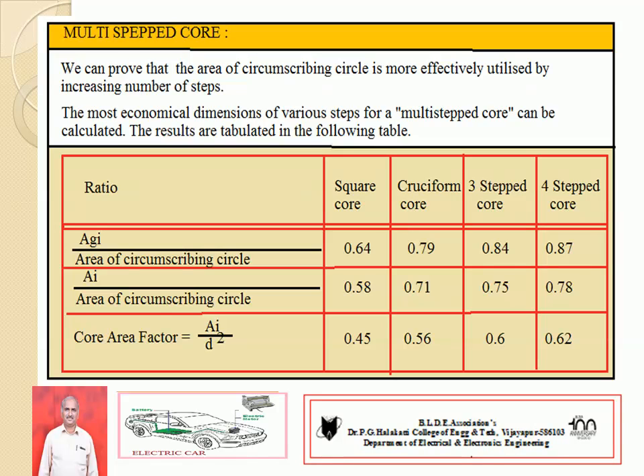As compared to square core, cruciform core is better. As compared to cruciform core, three-stepped core is better. As compared to three-stepped core, four-stepped core is better. The table shows that the area of circumscribing circle utilization reaches 0.87 in a four-stepped core. Hence, by increasing the number of steps in the core, it utilizes the core area more properly. In practice, stepped cores are more useful rather than square and rectangular cores. Thank you, sirs.